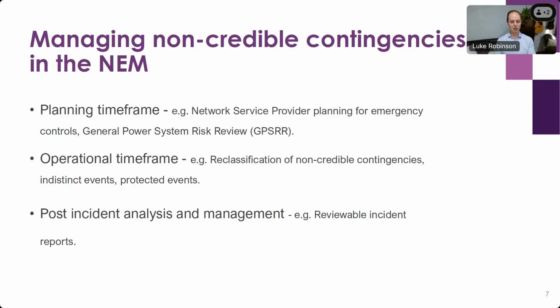In the operational timeframe, there are a number of means that can be used to mitigate the potential impact of non-credible events, and that's by reclassifying things as credible. So that might be, for example, a lightning storm adjacent to a transmission corridor which is known to be susceptible to lightning strikes, where a strike to the tower could cause a backflash over and double circuit fault onto the 2 circuits on a single tower. You might reclassify that tower if you know that it's susceptible to trip during a lightning event.